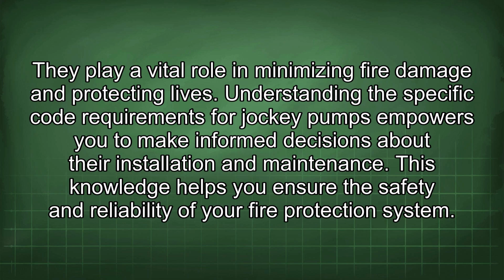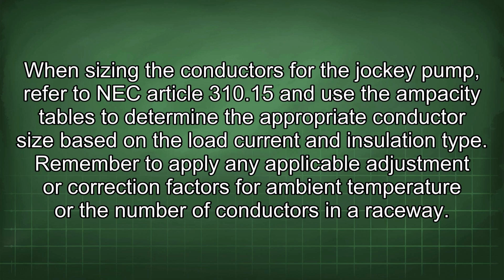Understanding the specific code requirements for jockey pumps empowers you to make informed decisions about their installation and maintenance. This knowledge helps you ensure the safety and reliability of your fire protection system. When sizing the conductors for the jockey pump, refer to NEC Article 310.15 and use the ampacity tables to determine the appropriate conductor size based on the load current and insulation type. Remember to apply any applicable adjustment or correction factors for ambient temperature or the number of conductors in a raceway.